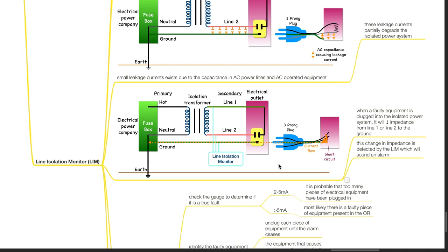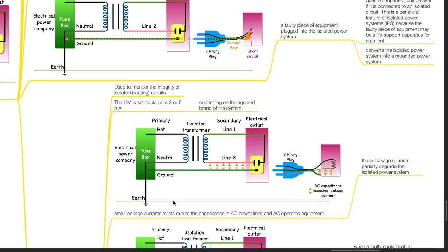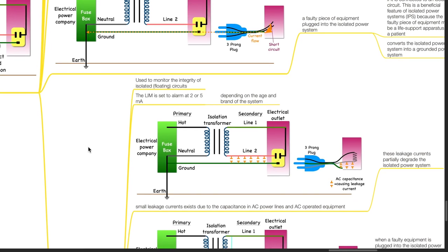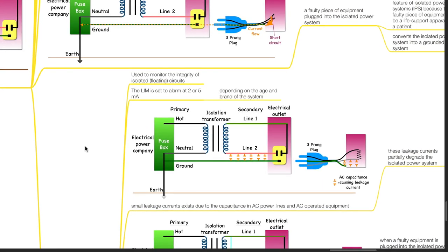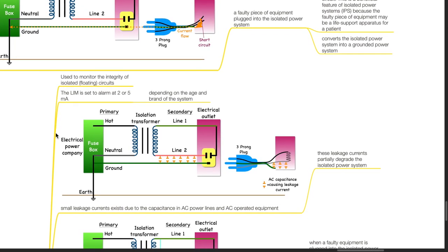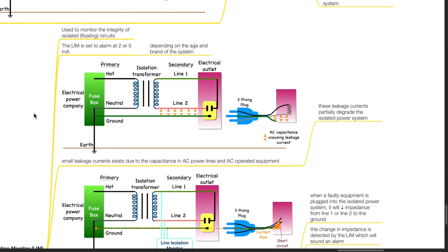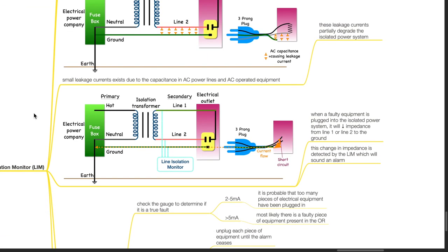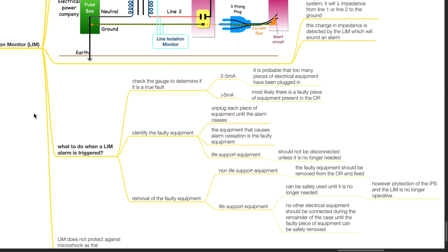Line Isolation Monitor is used to monitor the integrity of isolated floating circuits. The LIM is set to alarm at 2 or 5 milliamps depending on the age and brand of the system. Small leakage currents exist due to capacitance in AC power lines and AC operated equipment. These leakage currents partially degrade the isolated power system. When faulty equipment is plugged into the isolated power system, it will reduce the impedance from line 1 or line 2 to the ground. This change in impedance is detected by the LIM which will sound an alarm.